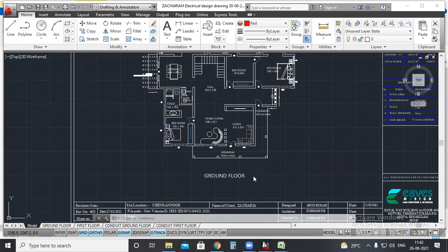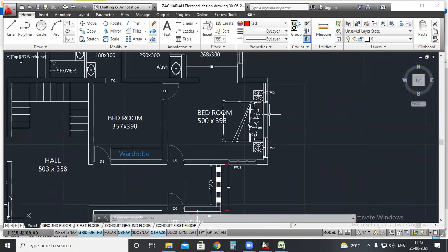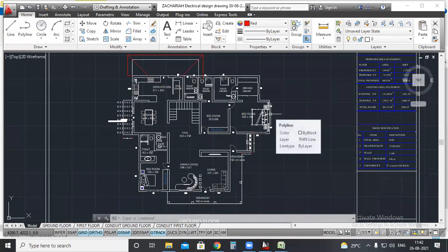Yeah, we have to provide a cabinet. Then only will we have the option for waterproofing. We have to provide a cabinet with IP43 rating, and we'll have a sunshade above this cabinet. If there is no provision for weatherproofing, then you have to consider the location, just as Adil told, under the veranda. But providing it in the veranda area obviously will not look good, because we'll be highlighting those spaces with the up and down lights and all.